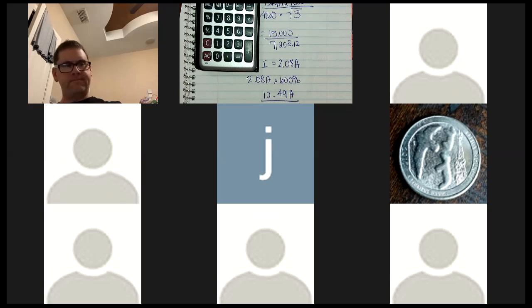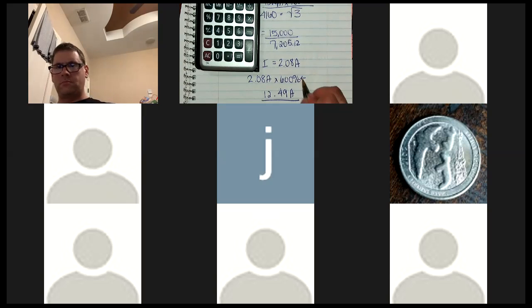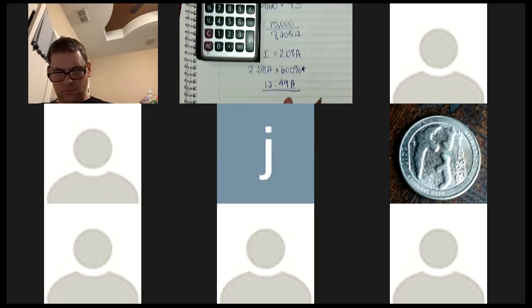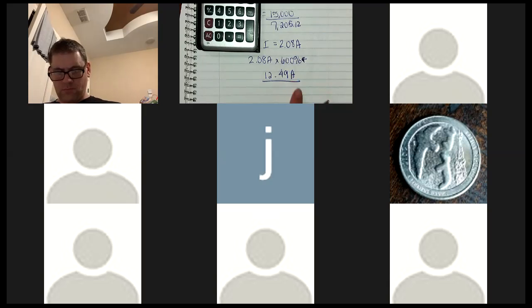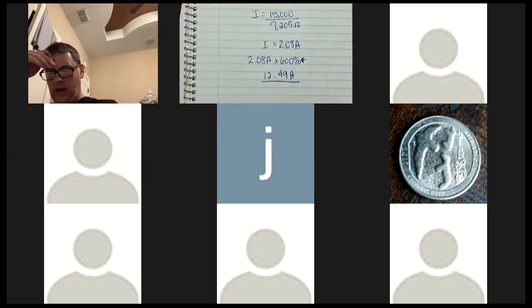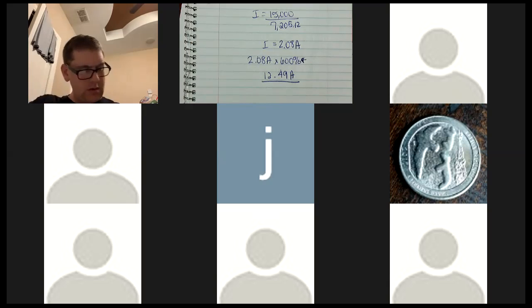240.6(A). Now remember, what happens right here with the 600% when we're trying to get the standard size? It's got to be set in accordance with the circuit breakers. So technically, if we need to, we can go to the next higher standard size rating, right? That's right. As long as it's in accordance with it. So let's look over here. I have 12.49. Either we go with 10 or we go with 15.